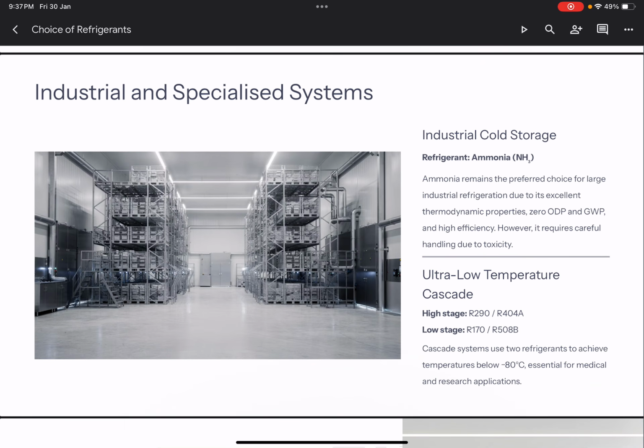In industrial and specialized systems, ammonia is much more common. It remains the preferred choice for large industrial systems due to its excellent thermodynamic properties, as well as zero ozone depletion potential and global warming potential, and a much better coefficient of performance. However, ammonia remains toxic. In a very specialized application like an ultra low temperature cascade system, two refrigerants are used, one in the high stage and the other in the low stage. The low stage is low boiling, the high stage is high boiling. That is typically for medical and research applications.